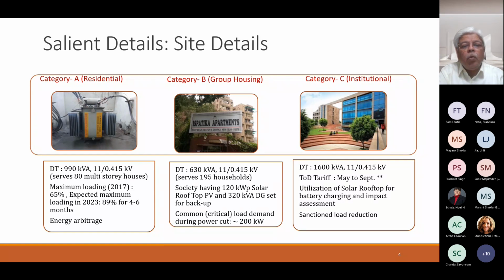For category B, the group housing society, a 320 kVA diesel generator set was being used to provide backup for critical loads, and the society also had 120 kilowatts of solar panels. The distribution transformer there is 630 kVA, serving about 195 households in a multi-story building with a lift and other critical loads, which we'll enumerate in the next slide.